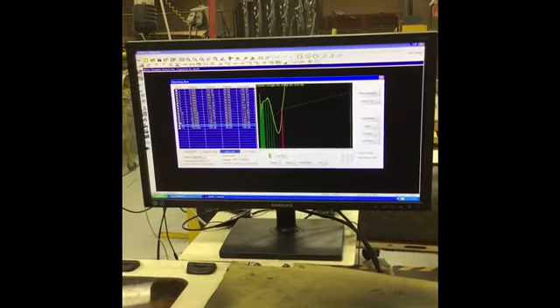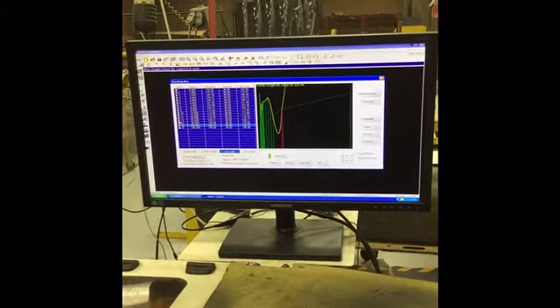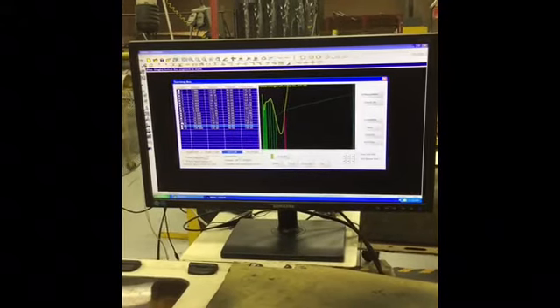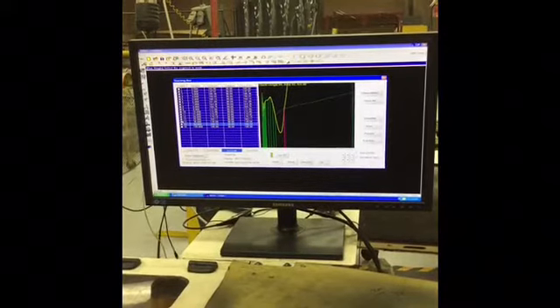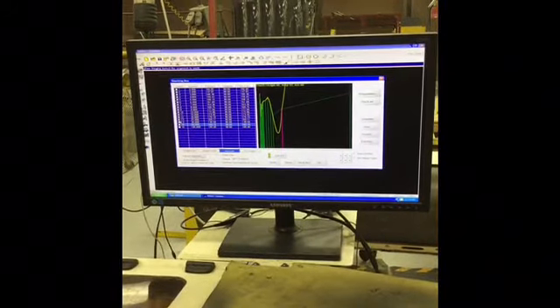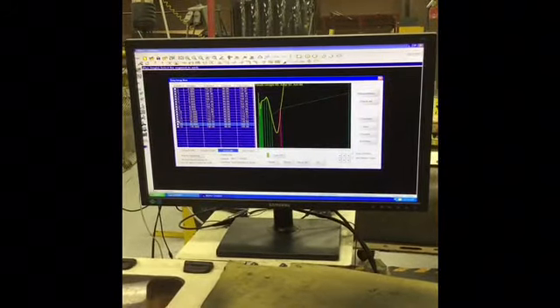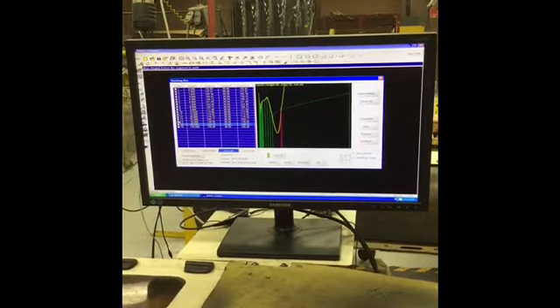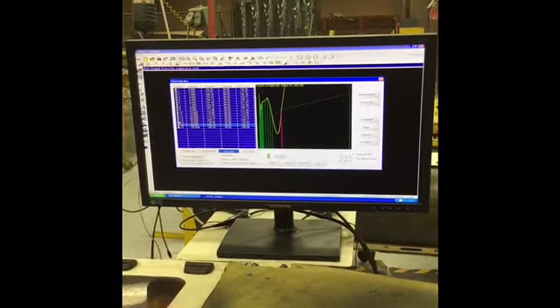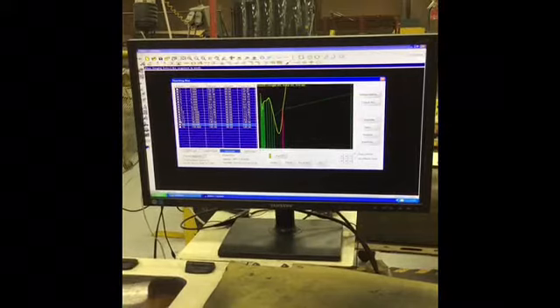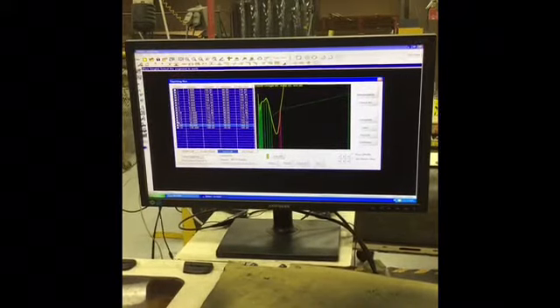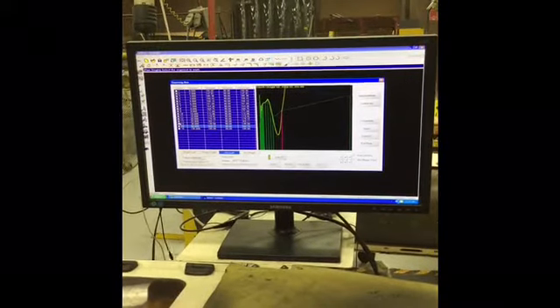If you want to do all of the sections, that's not going to hurt anything, but this will save you a little bit of time, because often you've got production going on. So if you don't need to do it, it can save time. If you've got to do a quick calibration, just make sure you get your main ones, so you keep the process going and you're not holding up the rule guides or the floor.